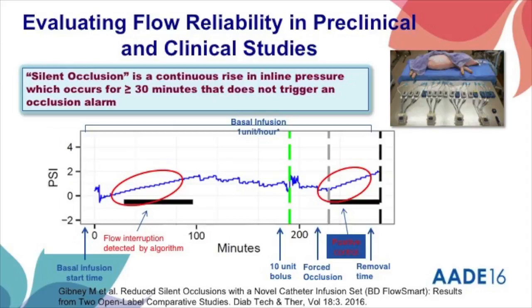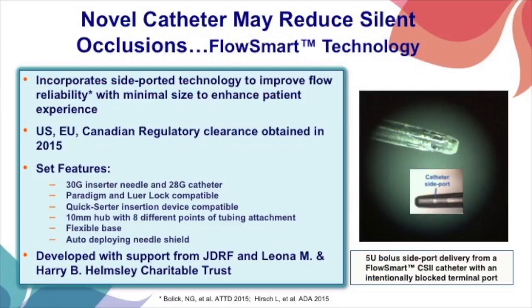So this really shows that we see silent occlusions, defined as a continuous rise in inline pressure which occurs for greater than 30 minutes that does not trigger the alarm. So this is really important data. We saw six or seven other slides that showed similar data. But what came out of this, with the support of the JDRF and the Helmsley Foundation, BD has developed a novel catheter that may reduce silent occlusions.